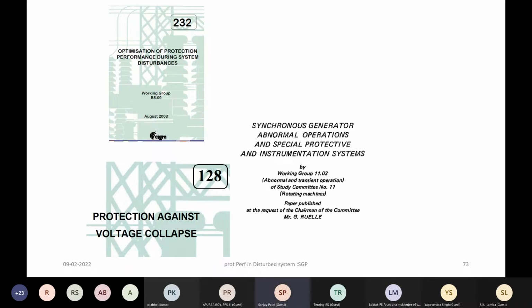Again, I'm giving you here 3 good references which you can read. There are 2 CIGRE reports. One is optimization of the protection performance during system disturbance, and there is also a report on protection against voltage collapse. For the hydro machines, there is a good CIGRE report also on synchronous generator, abnormal operation, and special protection and instrumentation systems. This working group report is also available, which you can refer to for more information on protection control aspects.